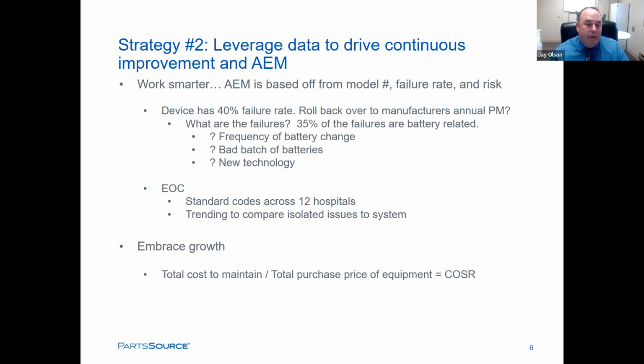It was one of the more intrusive joint commission visits, and it was nice to have because we did well. So as my chart here has—your device, if you went straight off your percent failures, we base our AEM off the model number, failure rate, and risk. If your device has a 40% failure rate, do you roll it back to the manufacturer's annual PM just because it hit that level? You've got to go back and look at the failures.